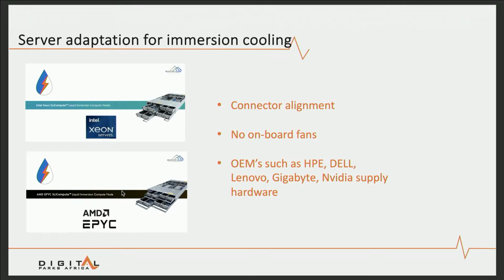Now, these liquids are very effective. They require, though, a few minor adjustments, and the OEMs have by now embraced these adjustments as well. Your server boards no longer require the onboard fans. They are used for air cooling on the server boards themselves, and the connectors are aligned on the outwards facing edge so that it's easy to immerse the server vertically into the tank and work on the connections from the top. So some minor adjustments, but as you can see here, the large OEM vendors have already adopted it and offer immersion-ready servers, and more high-performance vendors, high-performance equipment are making this technology available.